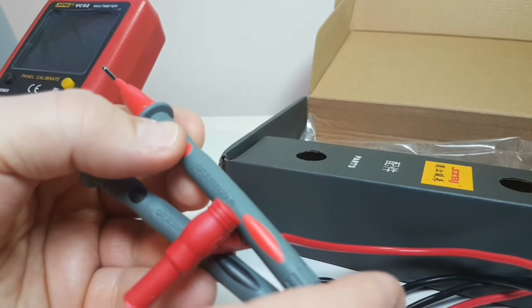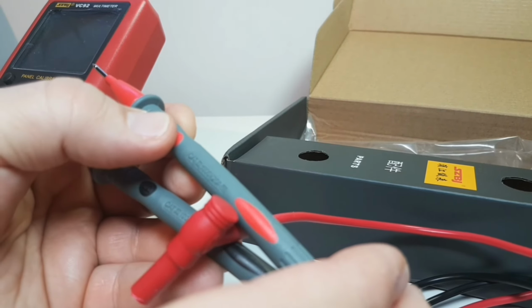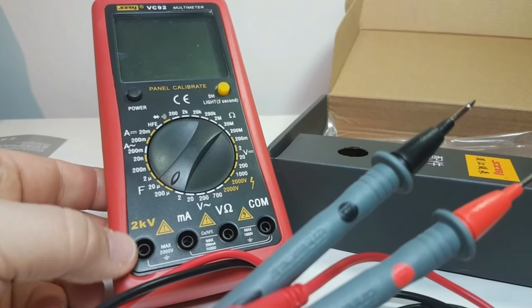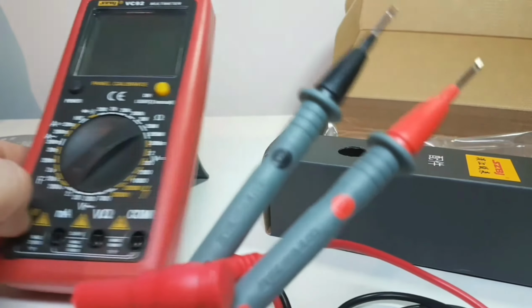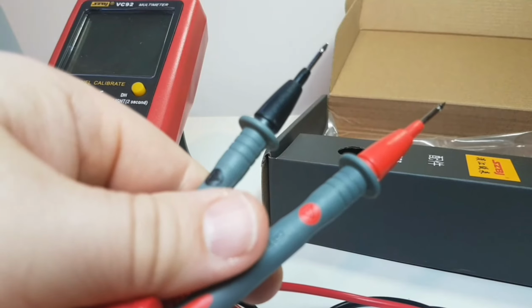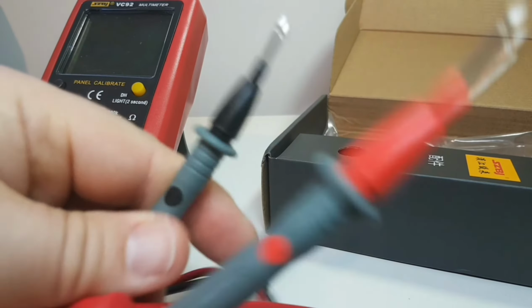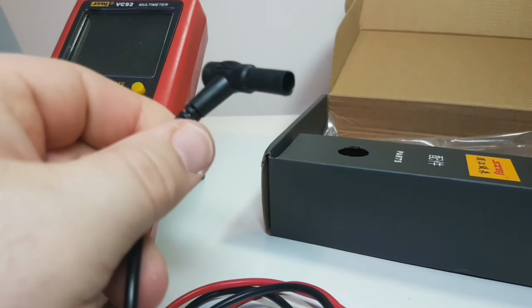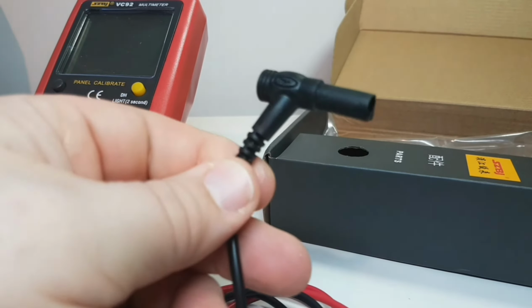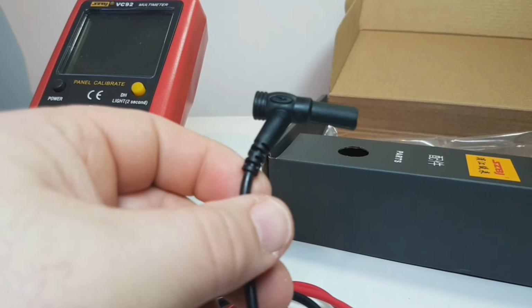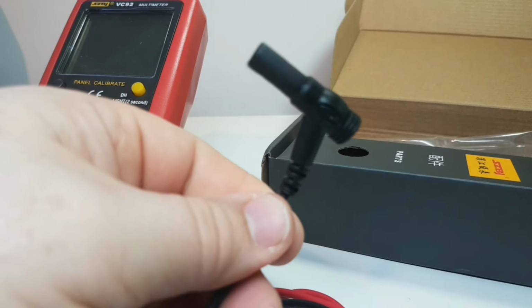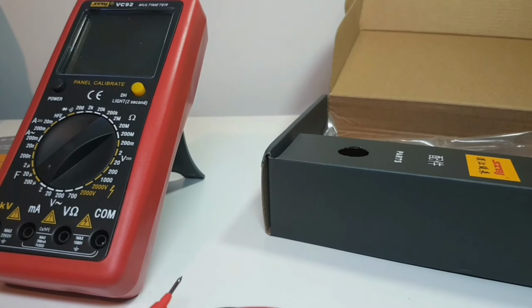These are rated as Cat 3, 1000 volts, 20 amps. So right away it's a little interesting considering this is a 2000 volt rated meter — they're shipping it with 1000 volt leads. Anyway, take a look at the shrouding. Not really that long considering the amount of voltage that they're expecting you to test with this meter.